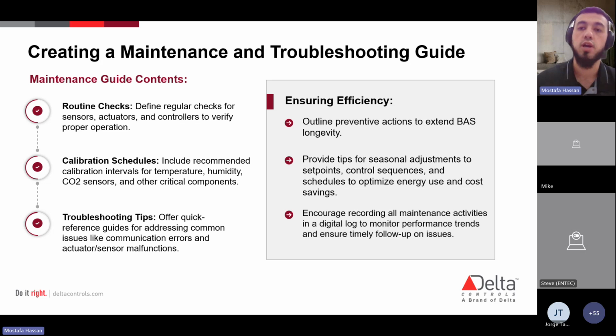This is going to make sure you have your customers' best interest at hand. You want to make sure that their building does not run into a lot of downtime because things are not calibrated or not checked regularly. And you're going to create recommended calibration schedules. These are part of some standards that are out there. You can follow that, or if you want to take it a step ahead, Guideline 36 will help you really build that spec, really build that sequence of operation. Then you could also put in some troubleshooting tips, based on experience and on that specific product manual, troubleshooting tips for that controller, things like that.